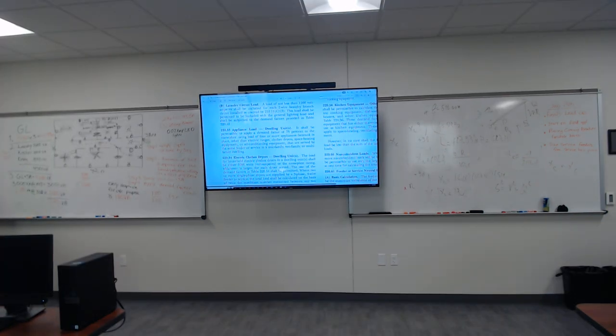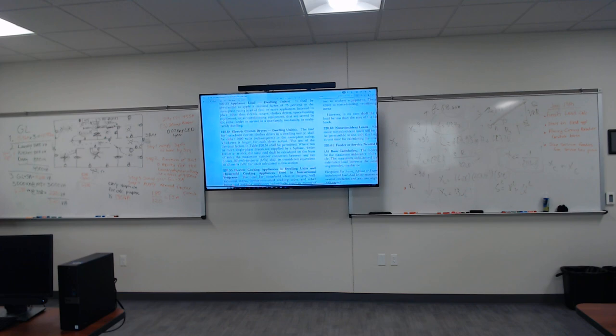All right. Now, number five is the dryer. Okay, I'm gonna go back to that article that mentions the dryer. All right, Article 220.54, electric clothes dryer for houses. The load for a household electric dryer in a dwelling unit shall be either 5,000 watts, VA, or the nameplate rating, whichever is larger for each dryer served.